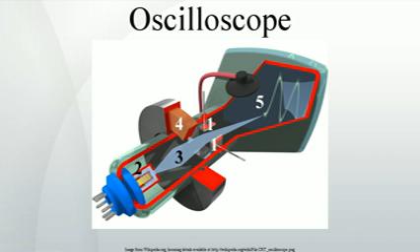Horizontal position control. The horizontal position control moves the display sidewise. It usually sets the left end of the trace at the left edge of the graticule, but it can displace the whole trace when desired. This control also moves the XY mode traces sidewise in some instruments, and can compensate for a limited DC component as for vertical position.